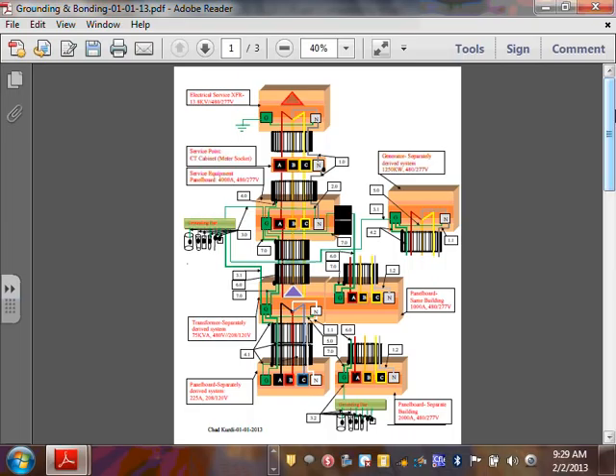Generators, you have an option. You can run them separately derived or not, and I'll say a few things about it. This is a separately derived system generator. We're going to bond and ground at the generator, and then tie it into the switchgear. Cool. Okay, so that's the big picture. And right in here, that little grounding bar.